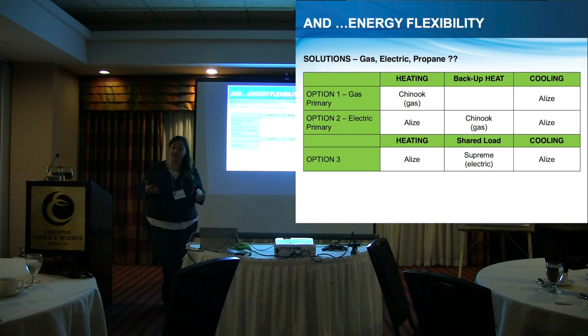Sometimes we end up in a house where they don't want to change the envelope, right? And so with other builders, our team is really good at saying, hey, you're really close to getting down to another size furnace. So instead of a 45, make a slight change to your envelope or HRV or your windows. Let's find that extra BTU, get down to a smaller furnace, and the potential is there that we could go into fewer duct runs because it's a smaller CFM. And often cooling dictates that as well.